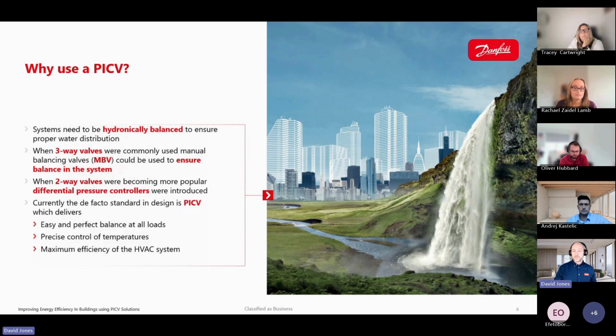However, as the industry moved towards energy efficiency and variable flow systems, two-way control valves became more common. These improve part load efficiency, but introduce a new challenge. As valves close, differential pressure in the system increases. This pressure fluctuation can lead to overflow in some branches, reduced valve authority, noise, and unstable control. So to manage this, differential pressure controllers were introduced to stabilize sections of the system and protect control valve performance. More recently, pressure-independent control valves, or PICVs, have become widely adopted. These combine flow limitation and pressure control in a single device, ensuring the design flow rate is maintained regardless of system pressure fluctuations. The result is stable operation at both full and partial loads, simplified commissioning, and improved control accuracy.